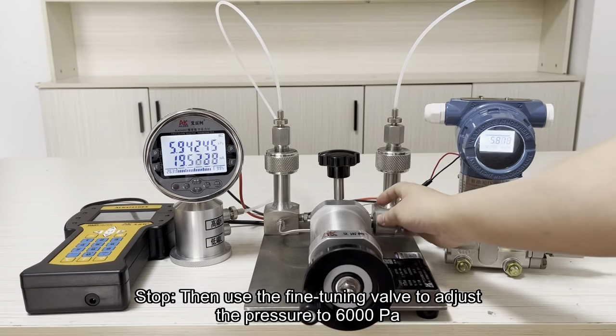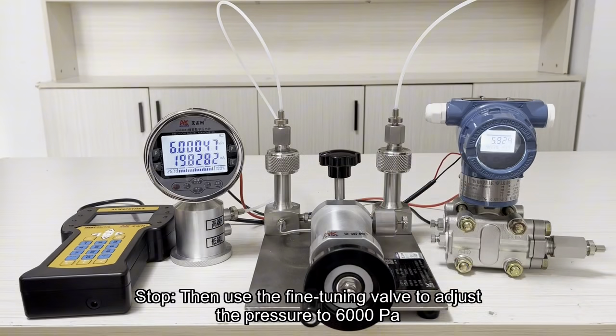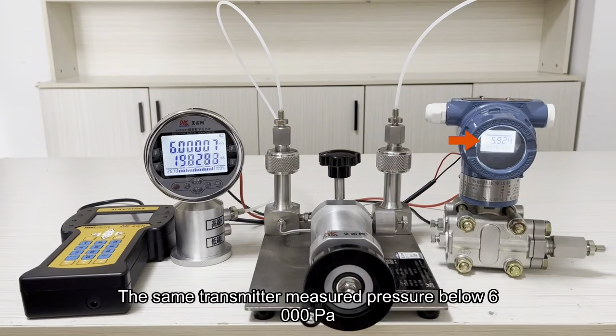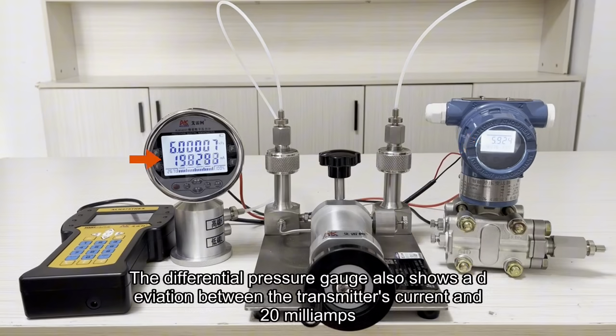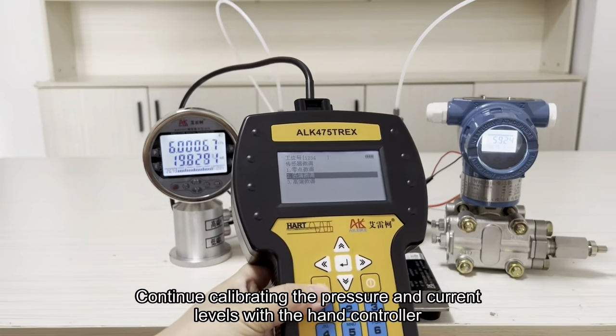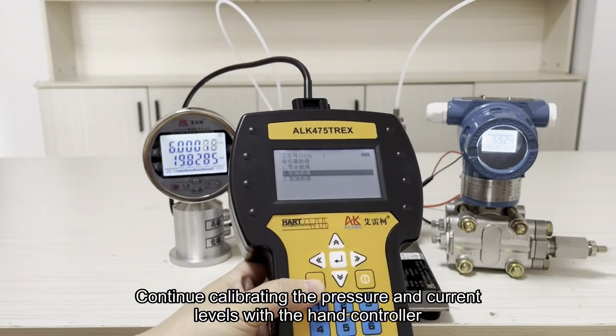Stop. Then use the fine-tuning valve to adjust the pressure to 6000 Pa. The transmitter measured pressure is again below 6000 Pa. The differential pressure gauge also shows a deviation between the transmitter's current and 20 mA. Continue calibrating the pressure and current values with the hand controller.